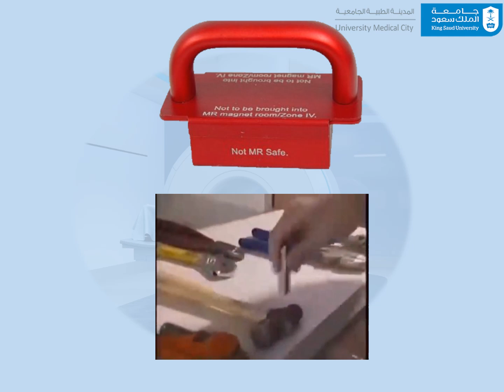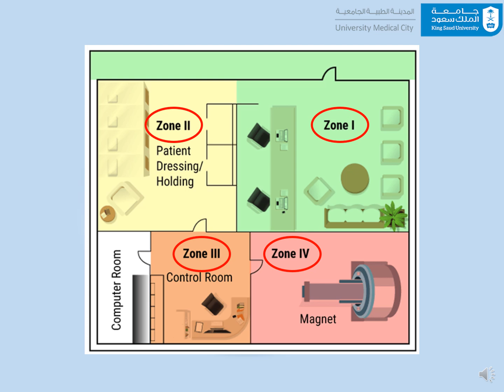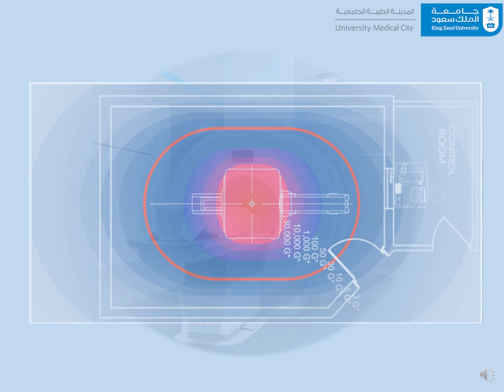The American College of Radiology has defined 4 safety zones within MRI facilities, numbered 1 to 4. The zones correspond to the increasing exposure to the magnetic field, and, therefore, the increasing potential safety risks. These zones are designed to ensure the safety of patients, staff, and visitors in the MRI environment. The controlled area for the magnetic field strength is established and defined around the MRI system's magnet. This controlled area must be clearly marked and designated. In a typical MRI system, the controlled area extends a few meters out from the center of the magnet.